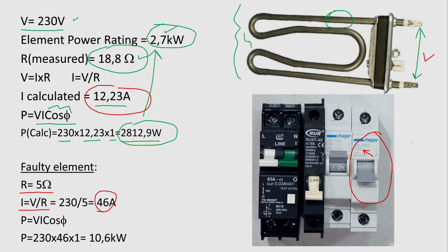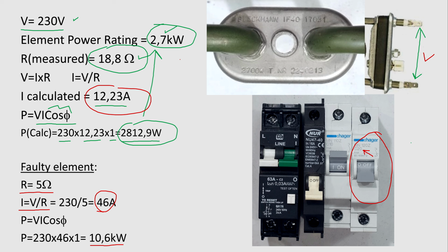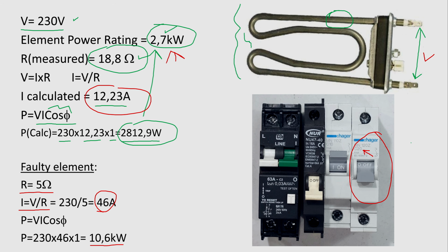If we just work out what the power would have been, this element would want to draw 10.6 kilowatts, which again is way above what was stamped on the body. So that tells you that the element is faulty. In this case, if you did get such a value of 5 ohms, it would trip both the overcurrent circuit breaker as well as your earth leakage or your RCD, because the current would exceed the overcurrent circuit breaker, but also your RCD would trip because the live and the neutral would be out of balance, because this current would be escaping from the body to earth.